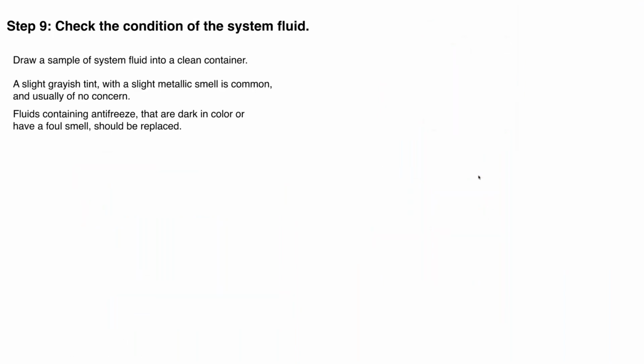Okay. All right, checking system fluid. This is becoming more and more important in hydronic systems, especially as we get into heat pumps and modulating condensing boilers, where whatever comes out of the tap isn't necessarily good enough to go into that system. Typically, you want to draw a sample into a nice clean glass container. It's common, especially in boiler systems, cast iron boiler systems, steel boilers, that water might have a slight grayish tint to it and a metallic smell. Usually that's not a problem, but if you're seeing like a black syrup come out, that's definitely a problem.